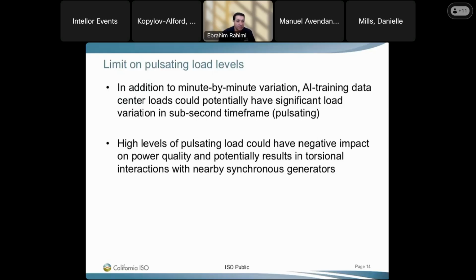We call it pulsating, but that's the nature of how these operate at the computational level. If we have a lot of pulsating load with many projects in close proximity, it could have negative impact on power quality and potentially result in torsional interaction with nearby synchronous generators. So we need a limit on that. More detail coming up later.